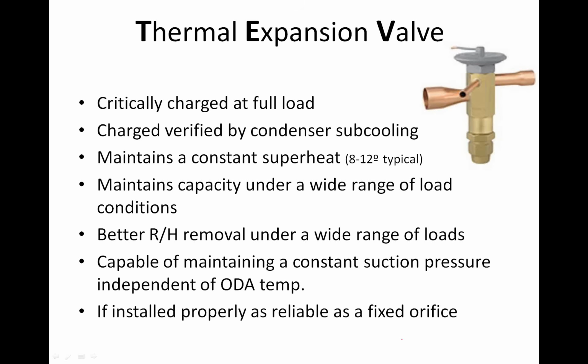And what this means is, with a TXV, as it gets hotter and hotter outside, the condenser pressure goes up, and the TXV simply closes down, right? The suction pressure is not going to get driven up with an increase in outdoor air temperature because the TXV has the capability of actually closing down. And now it doesn't maintain suction pressure. The suction pressure a TXV sees is simply a function of the load.